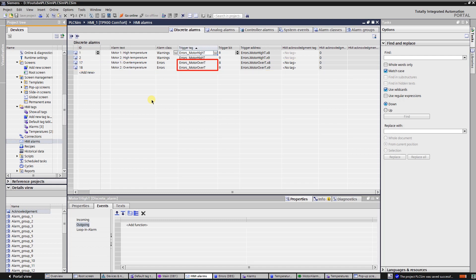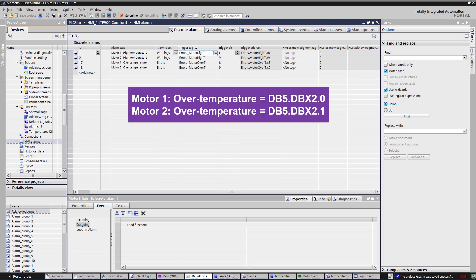Trigger tag motor over temperature, and trigger bits are bits number 0 and 1 of the trigger tag. It means that motor 1 over temperature alarm is DB5 DBX 2.0, and motor 2 over temperature alarm is DB5 DBX 2.1.